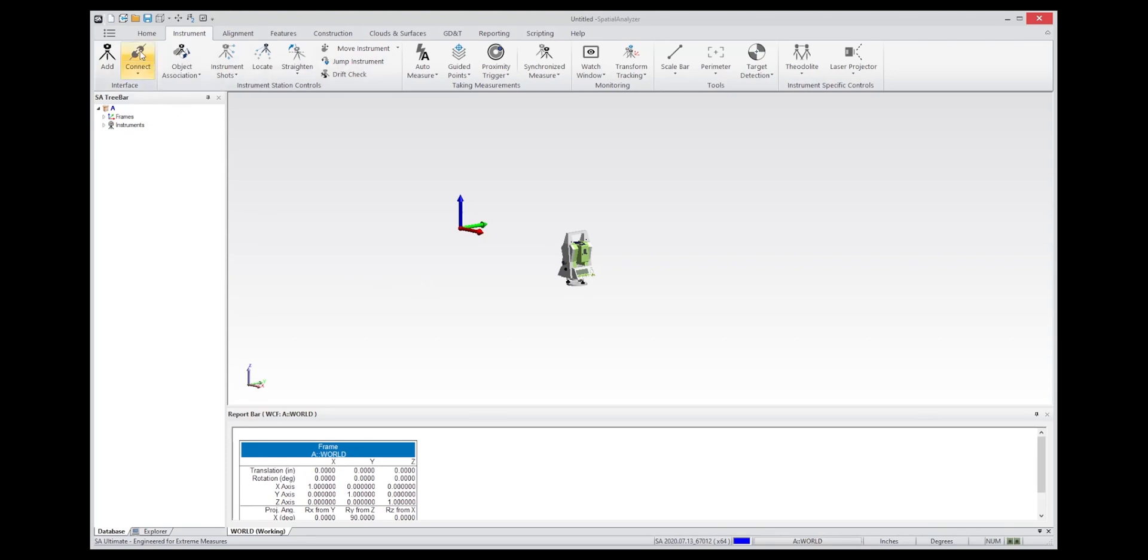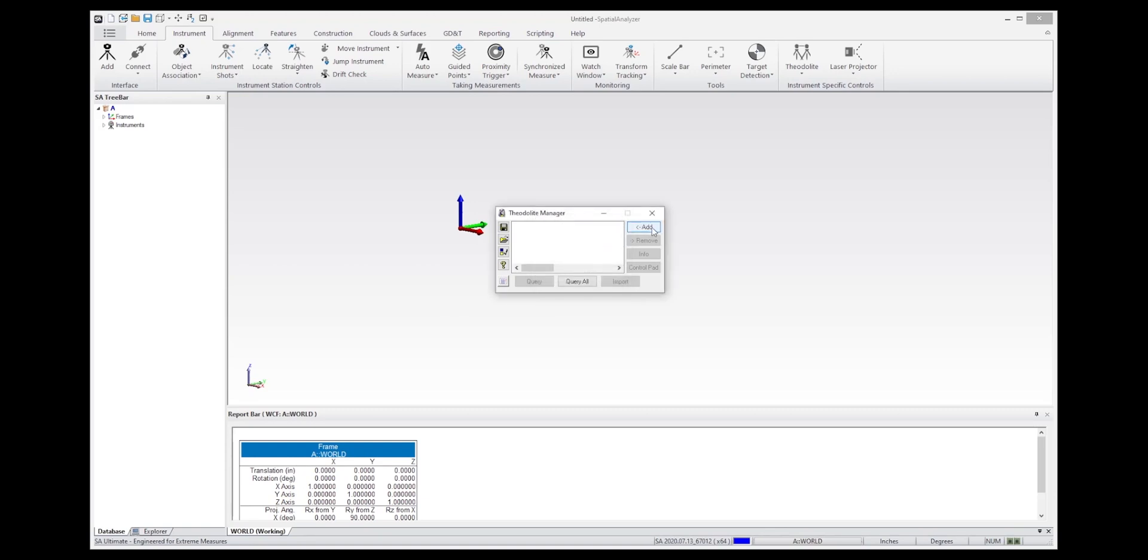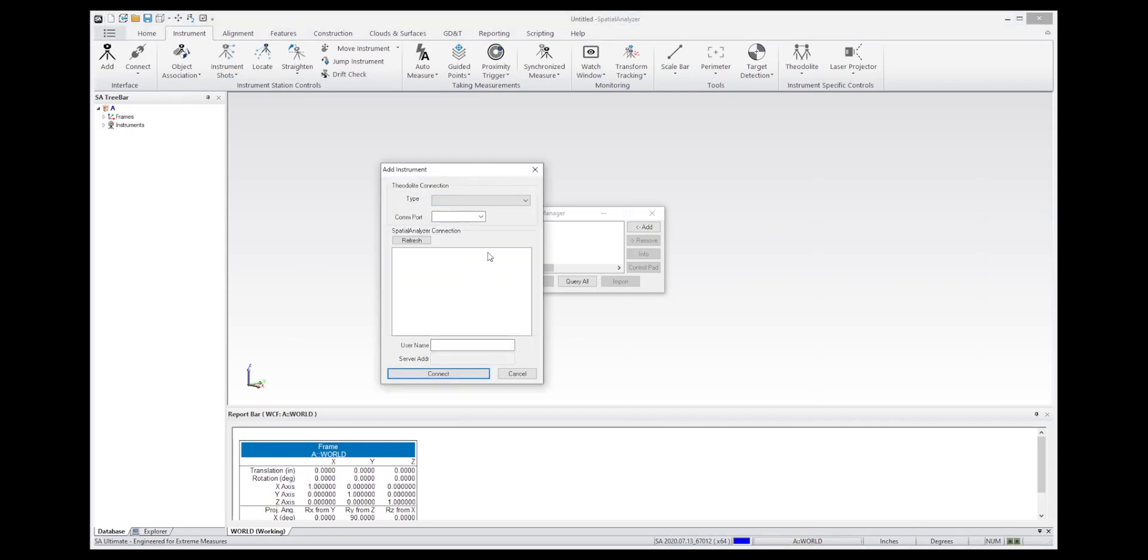And to connect to the instrument, hit the Connect button, which will bring up the Theodolite Manager. And this seems a little bit redundant, but the Theodolite Manager allows you to control multiple instruments at one time, which can be useful for Theodolite applications. So hit New Instrument Setup, Add. And this will look to see if there is an instrument model within SA that you can connect to.